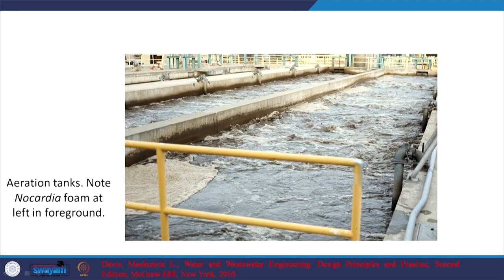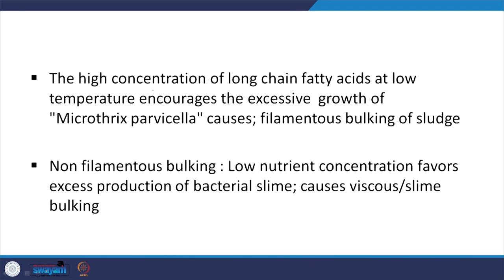You can see the kind of foaming associated with Nocardia. High concentration of long-chain fatty acids at low temperature encourages excessive growth of these bacteria, which again leads to filamentous bulking. There is another kind called non-filamentous bulking, where low nutrient concentration favors excess production of slime, resulting in viscous slime bulking.